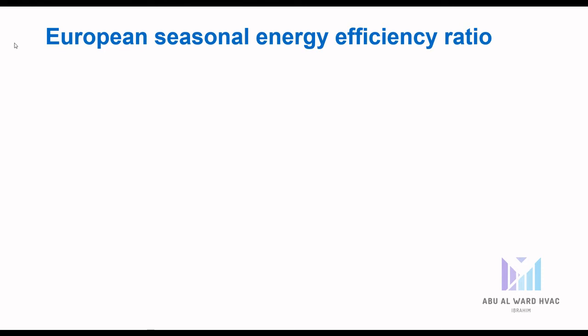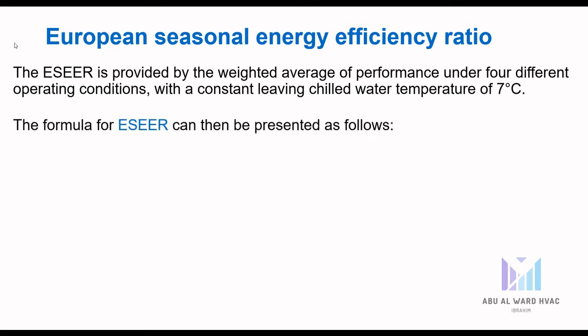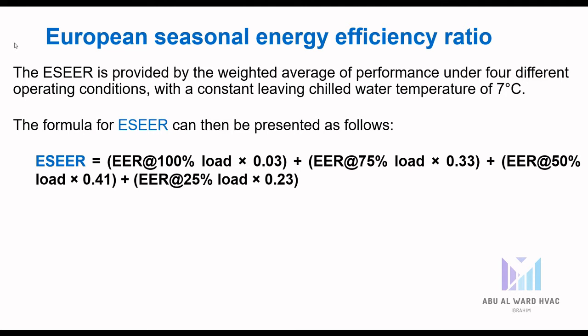The European Seasonal Energy Efficiency Ratio (ESEER) is provided by the weighted average of performance under four different operational conditions with a constant leaving chilled water temperature of 7°C. The formula is: ESEER = (EER at 100% load × 0.03) + (EER at 75% load × 0.33) + (EER at 50% load × 0.41) + (EER at 25% load × 0.23).